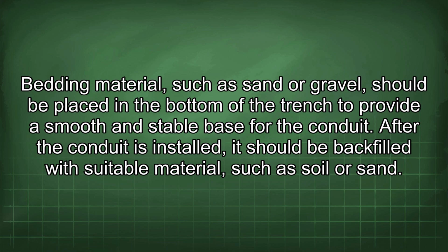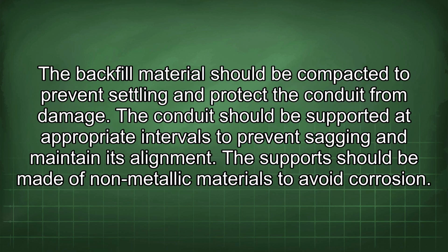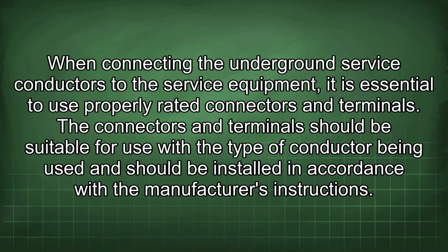After the conduit is installed, it should be backfilled with suitable material such as soil or sand. The backfill material should be compacted to prevent settling and protect the conduit from damage. The conduit should be supported at appropriate intervals to prevent sagging and maintain its alignment. The support should be made of non-metallic materials to avoid corrosion. When connecting the underground service conductors to the service equipment, it is essential to use properly rated connectors and terminals.